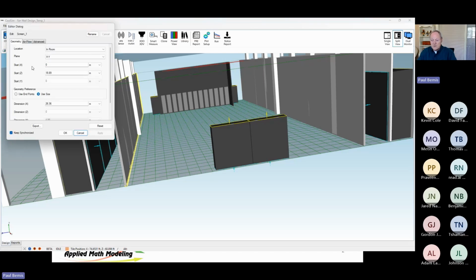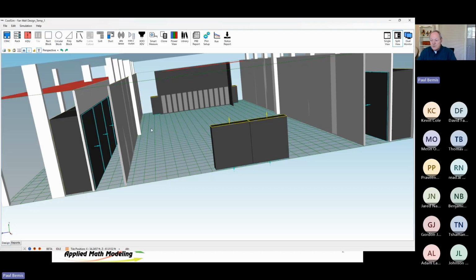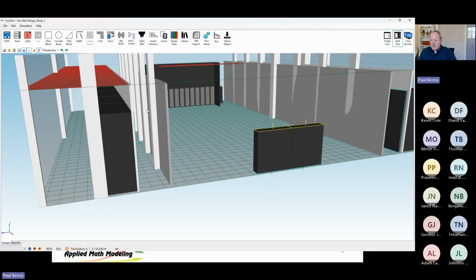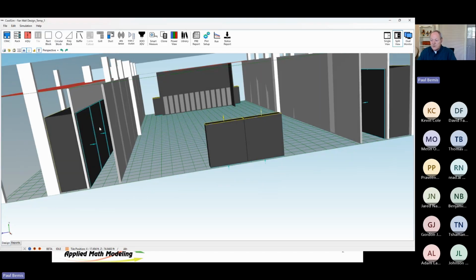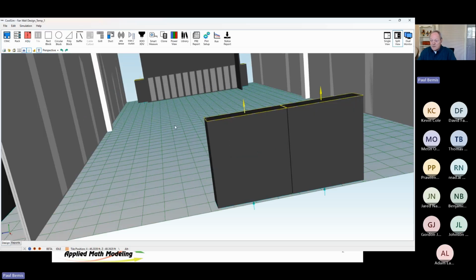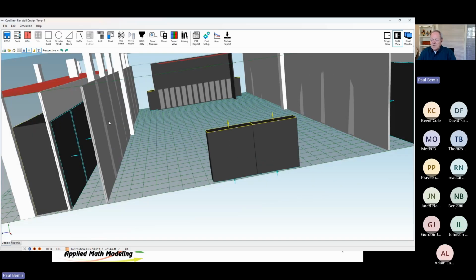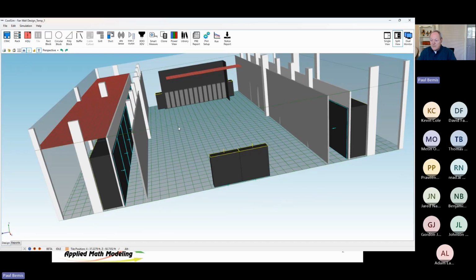One of these fan walls goes down. They want that air to be distributed. It doesn't have a lot of resistance. We generally set them for about 70% open, but it does supply some diffusion of the air on the back side of this from a pressure point of view, so that if I lose one of these units, then I get the help from the other one because it's coming in this direction a bit more due to that resistance. So a little bit of flow impedance can help diffuse the air.